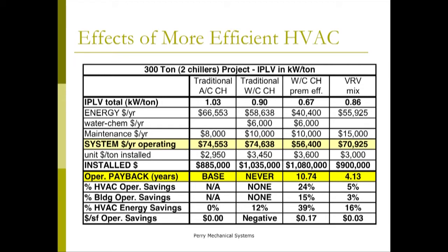The other system I'm looking at here is the VRV system, the variable refrigerant volume we were talking about. So if you look at the operating costs and payback here, I've factored in some maintenance costs, so it's not just energy based. Also, for the water-cooled systems, I've factored in water treatment costs, since that's a significant impact on a water-cooled system.